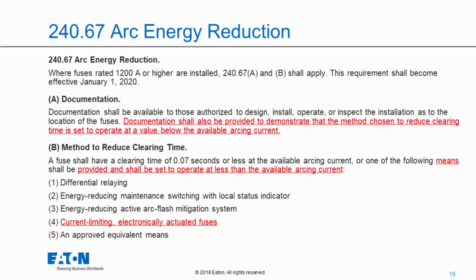So what's required? If I do have fuses 1,200 amps or higher, as you can see, the effective date is January 1, 2020, and they put that effective date in when they put it into the 2017 code because the solutions that they list there in Part B of 240.67 did not exist. So that gave manufacturers time to develop products that would comply if the fuse cannot provide the required clearing time. However, if you're on the 2017 code, we're well past January 1, 2020. I'm sure everyone is thankful we're well past 2020 now, given the current situations we're dealing with. So this is a concern whether you're on the 2017 code or the 2020 code. It's just the amount of detail you have to provide, as you can see.